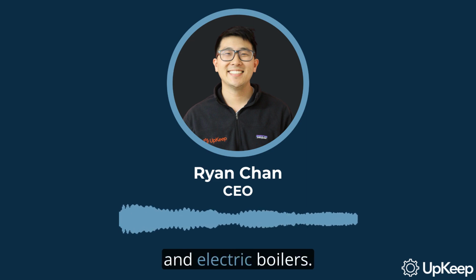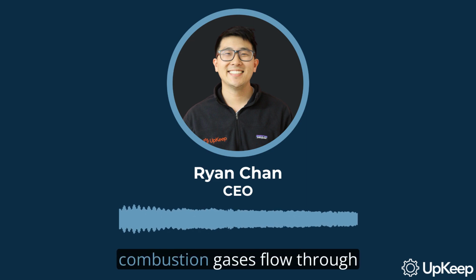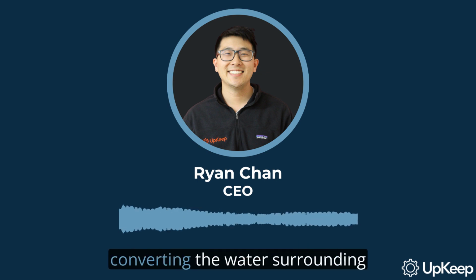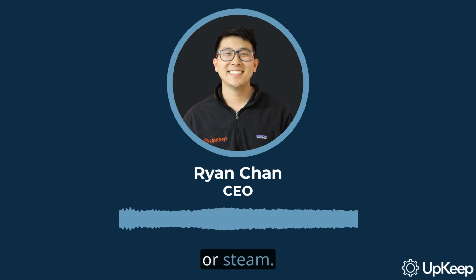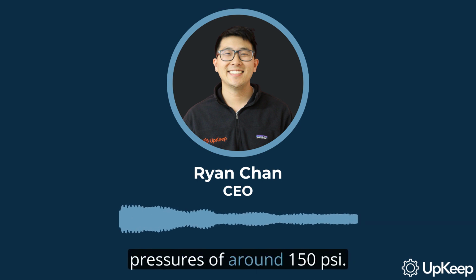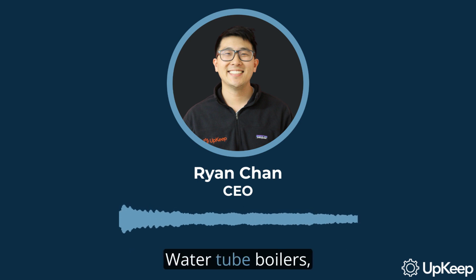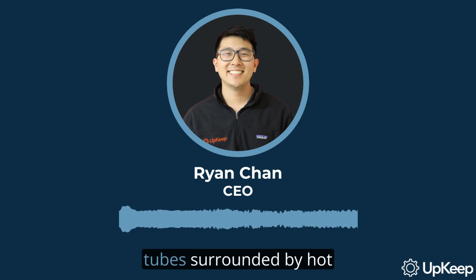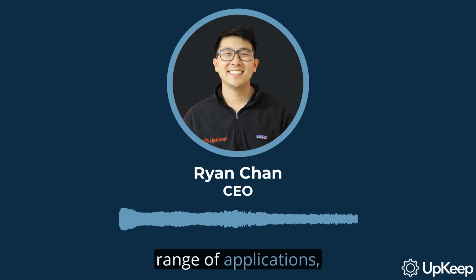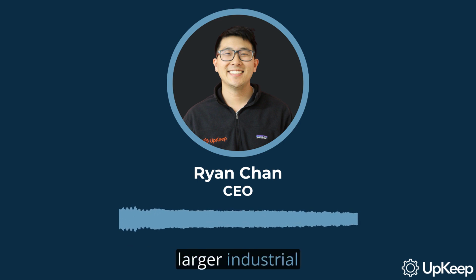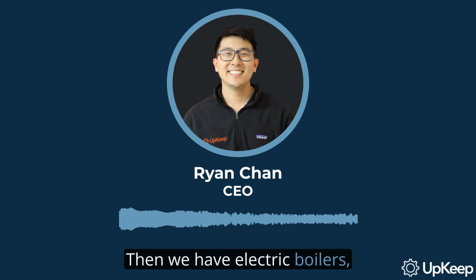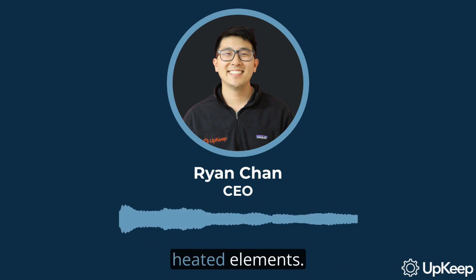Let's discuss the three main types of boilers: fire tube boilers, water tube boilers, and electric boilers. Fire tube boilers let hot combustion gases flow through tubes submerged in water, converting the water surrounding the tubes to hot water or steam. They operate at relatively low pressures of around 150 psi. Water tube boilers, on the other hand, allow water to pass through tubes surrounded by hot combustion gases. They can handle significantly higher pressures of up to 3,500 psi and are used in a broader range of applications, from small residential uses to larger industrial utility classes. Then we have electric boilers, which generate hot water or steam from electrically heated elements. They are typically used in heating, ventilation, and air conditioning applications.